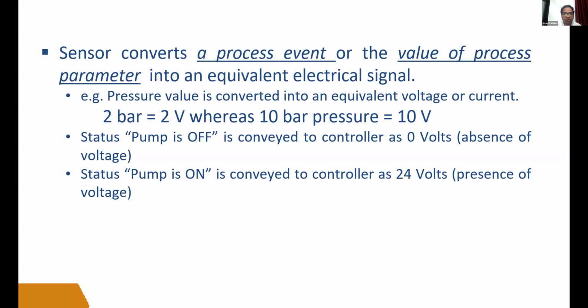You will ask me why there is a need to convert that information into the electrical signal. Because the controller understands only electrical signal. That's why the sensor gets the information and that information is converted into electrical signal. For example, suppose there is a pressure sensor. If you want to measure the pressure, the sensor will take the information in bar. Suppose there is 2 bar pressure, and that sensor will convert that information into electrical signal. Electrical signal means voltage or current. So a 2 bar value is converted into 2 volt, or we can say a 10 bar pressure value is converted into 10 volt. This is the very simple working principle of the sensor, guys.